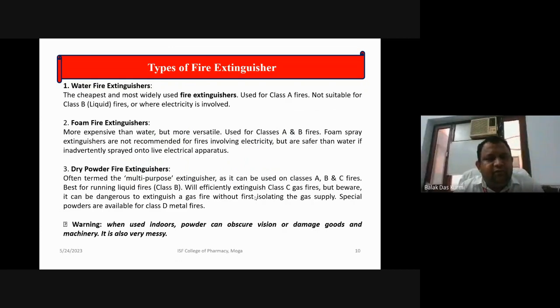Number two, foam fire extinguisher. It is more expensive than water but more versatile. This is used for class A and class B fire both. Foam spray extinguishers are not recommended for fire involving electricity, but these are safer than water if inadvertently sprayed onto live electrical apparatus. Number three, dry powder fire extinguisher, often termed the multi-purpose extinguisher, as it can be used on class A, B, and C fire.